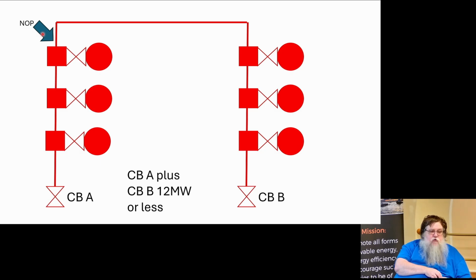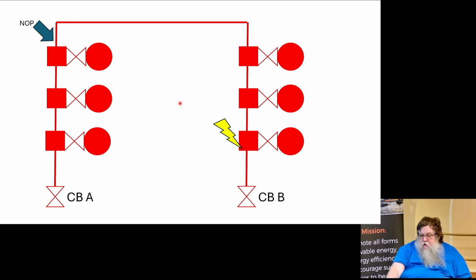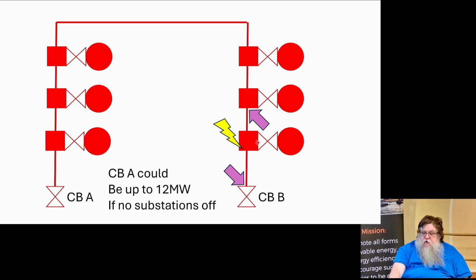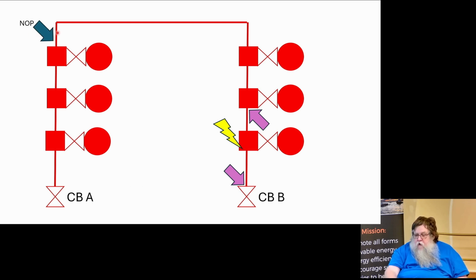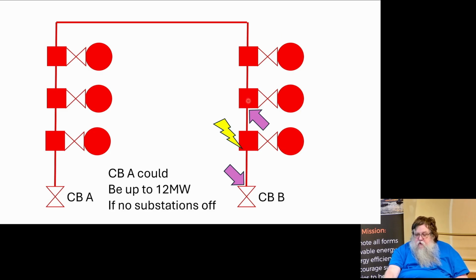If we get a fault on one of these circuit breakers, so the fault occurred at this substation, this circuit breaker would trip, all these folks would go off, and you'd lose more than 1 megawatt. And what happens is we go out, we've got 3 hours to do this in, we work out where the fault is, and we open switches here and here to isolate that fault. And then we close that normal open point that was there. So the normal open point is closed. We've now got all these on, and we've got up to 1 megawatt off, and that 1 megawatt is down to repair time, just as it was right from the start when we talked about the first thing.